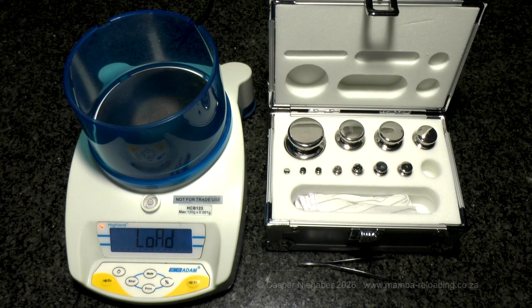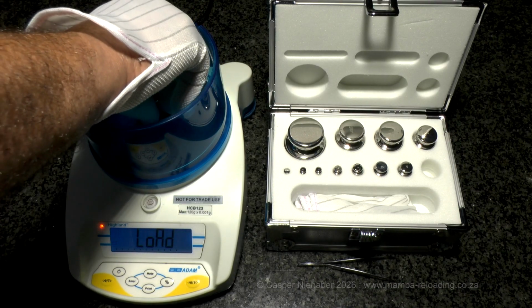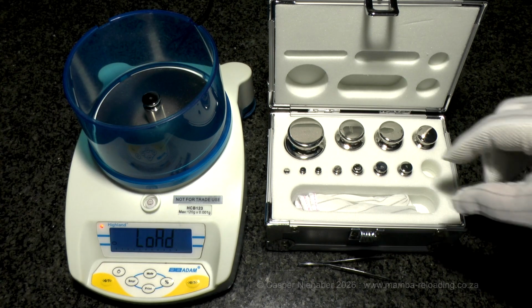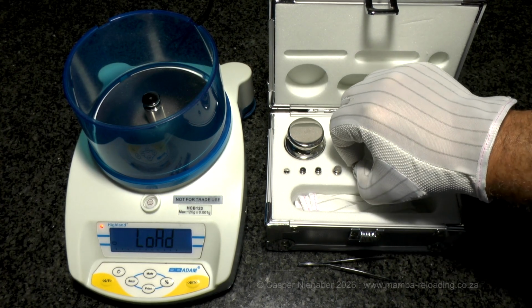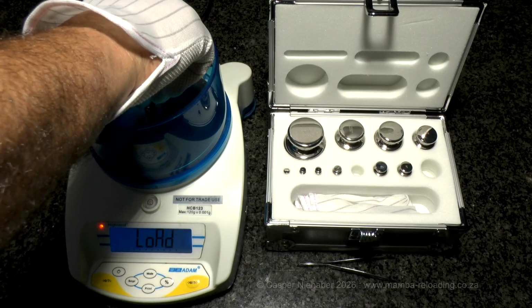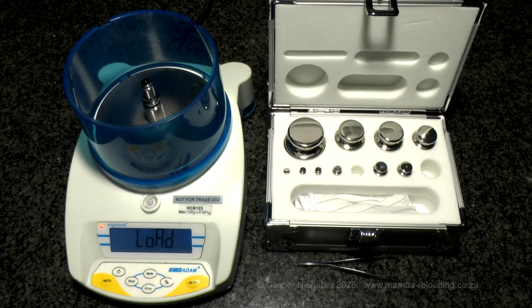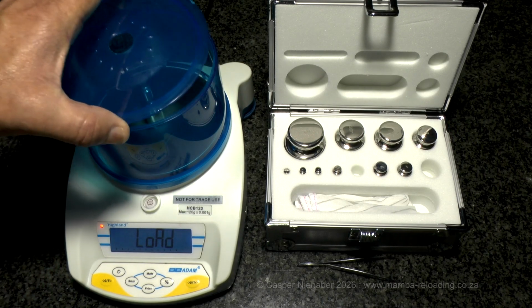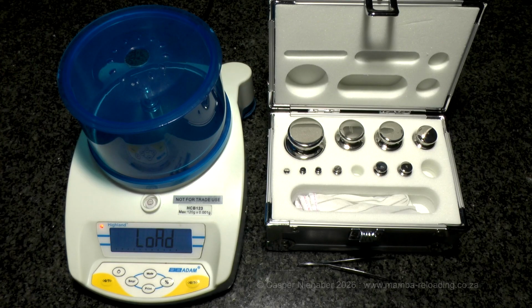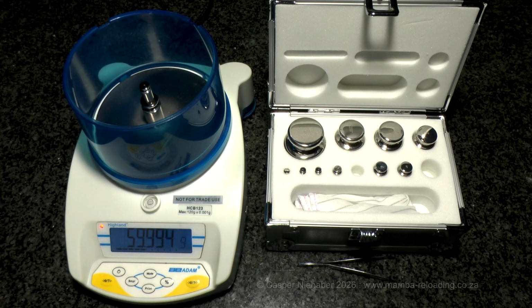Open the draft shield and carefully place the 50 gram test weight in the center of the pan. Remove the 10 gram test weight and place it carefully on top of the 50 gram weight, bringing the total to 60 grams. Close the draft shield and press the yellow Zero/Tare button to begin calibration. The display will show Pass, followed by 60 grams. Remove both weights carefully and return them to the case.